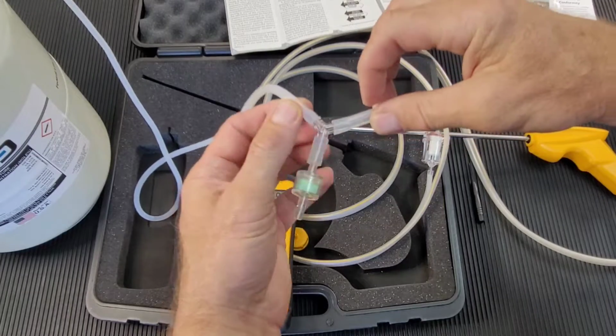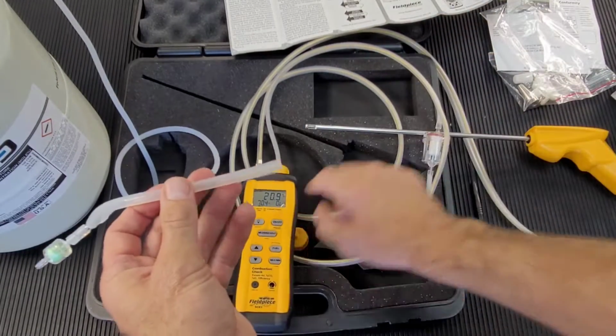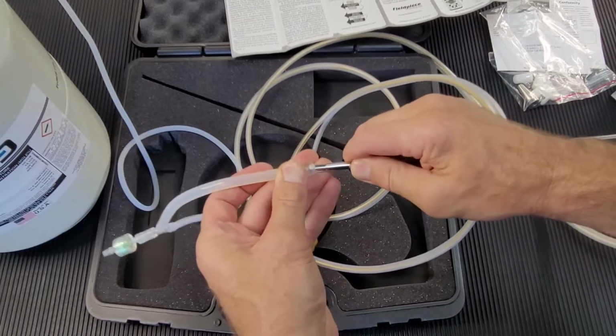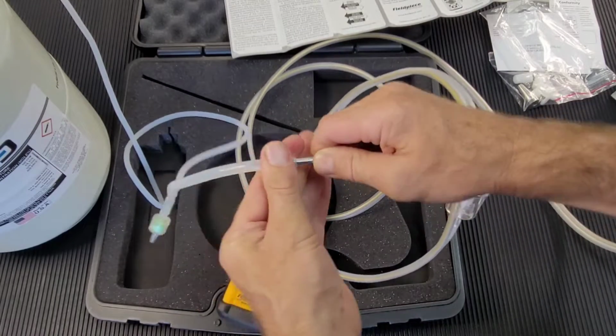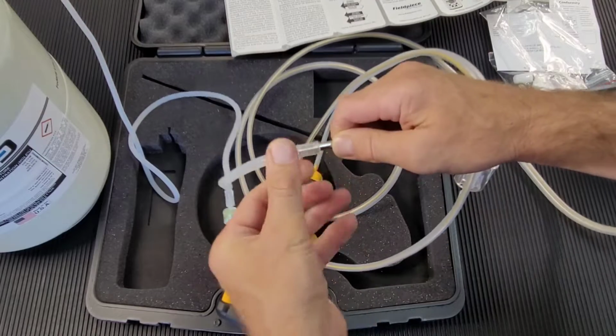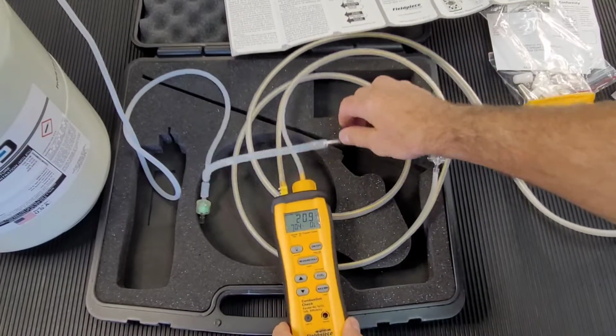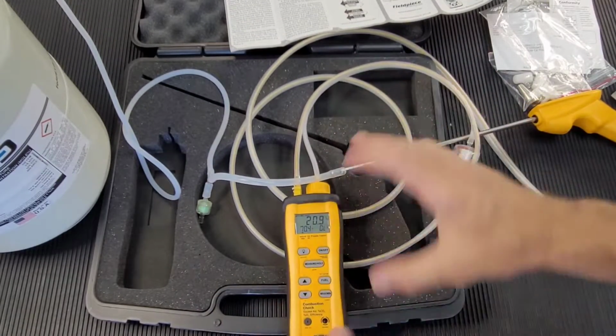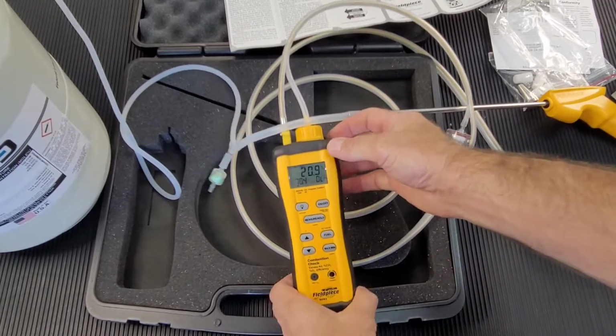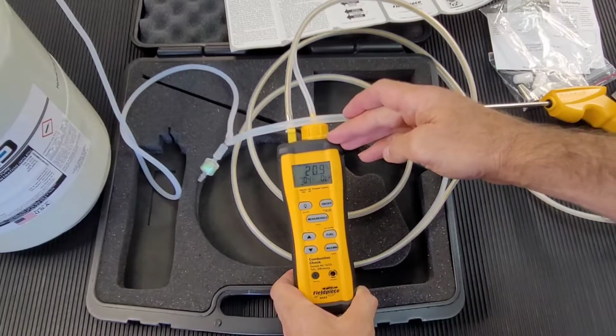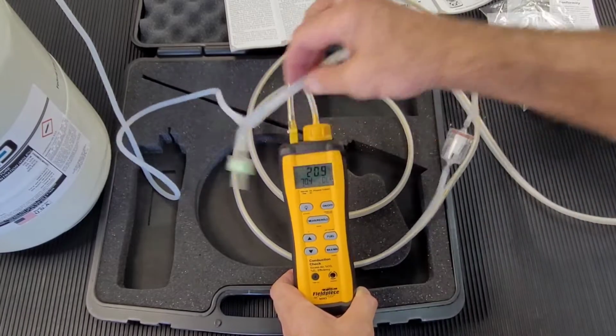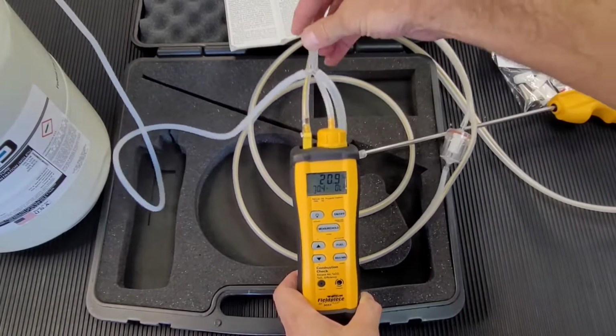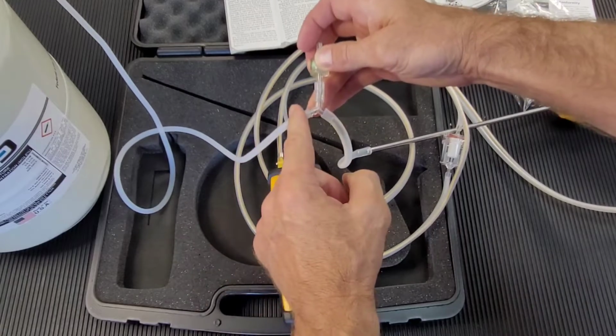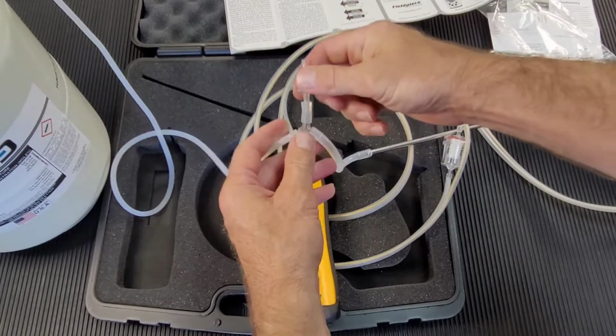Okay, folks, so I've got my gas coming into my T-piece. T-piece is very important whenever you're testing. Let me put that on hold. With a probe system, or gas detection system with a micro pump, you don't want to be forcing air in, or constricting air to the micro pump. You don't want to be stressing it either way, positive or negative, because it's set at a certain flow, and it should remain at that flow. So the way we can regulate that is with the T-piece, okay? If I bring in too much air, the excess will come out from this T-piece. If I don't bring enough air, it's going to be drawn into the pump.